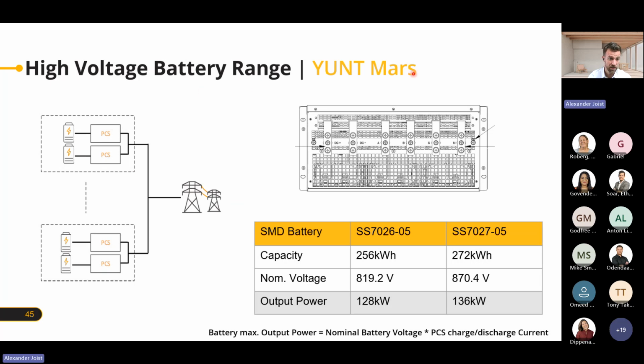That's the calculation of the PCS, sorry. So what we also can do here is, as you can see, we can have multiple systems, and then they're all connected to the loads, to the grid for arbitrage or whatever we need. So we can parallel multiple of the systems. That's the back of it. We can see the DC connection, then L1, L2, L3, as well as the neutral. So it has a neutral connection, which is important to build up a grid. Some PCSs don't have neutrals, so they need a transformer, but this PCS has a neutral, so it doesn't need the transformer necessarily, just as explained.